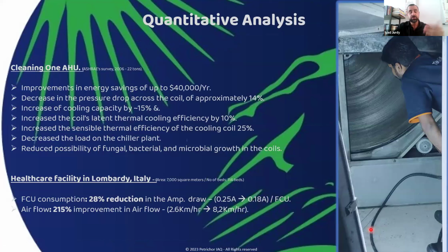These findings, what I just presented, we really didn't reinvent the wheel here. This has been done by ASHRAE themselves about 20 years ago, and they've noticed the same things. They did HVAC and AHU sanitization and cleaning, and found improved savings in electric cost by $40,000 a year, a decrease in pressure drop, increased cooling capacity by about 15%, thermal efficiency improvement with clean coil and clean fan by about 10%, sensible thermal by 25%, and latent by about 12% as well—very important for highly humid regions like Dubai. Obviously, it also reduces fungal and bacterial load.